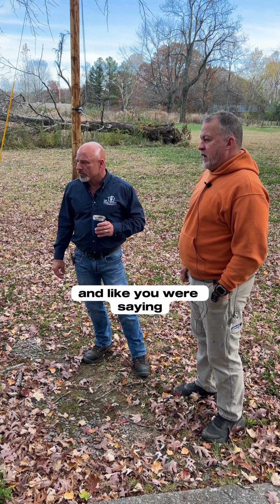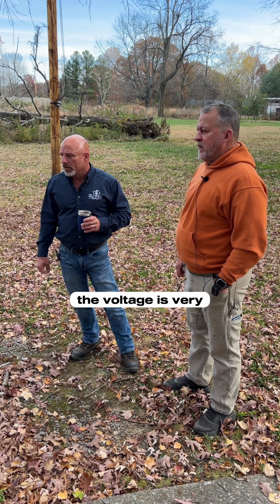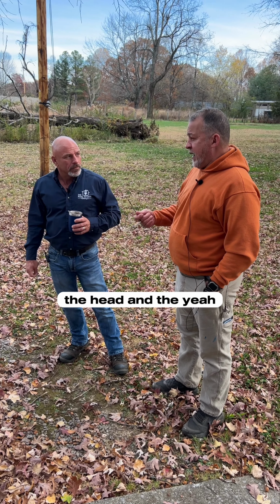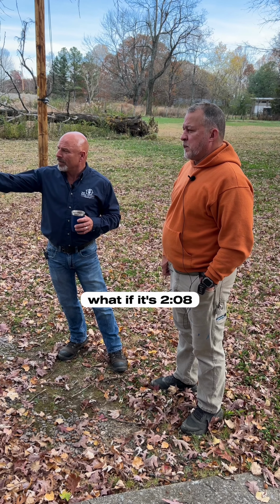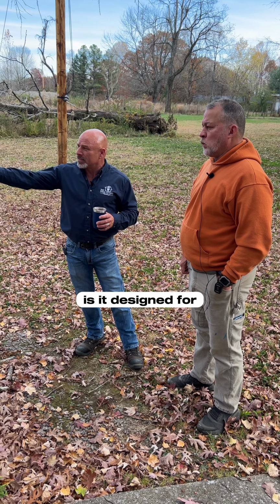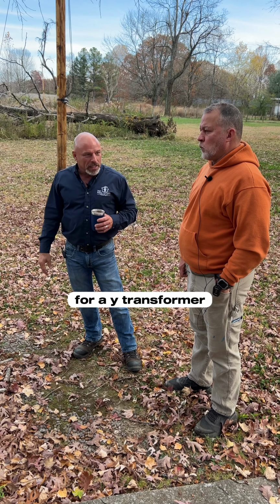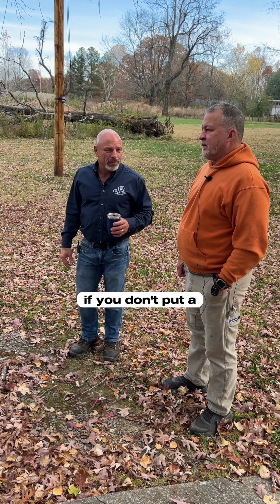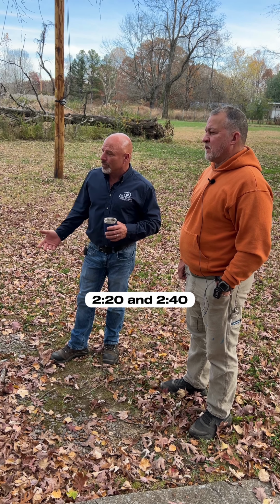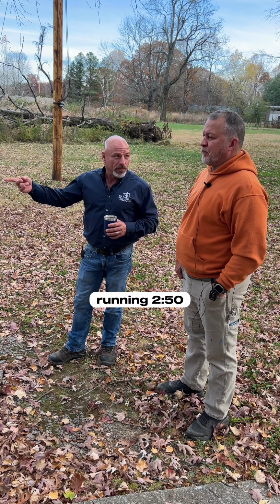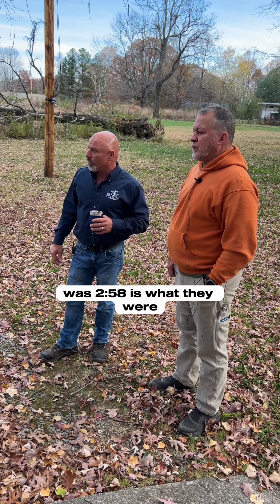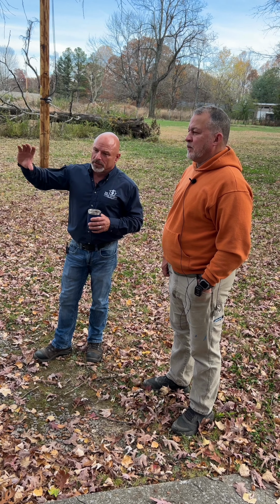And like you were saying, the voltage is very important to match the head and the unit. If it's 208, that tells us it's designed for a Y transformer, because that's what gives you 208. If you've got a Delta transformer, you're going to have between 220 and 240. Oh, and these are running 250 - I think it was 258 - because it was pushing 10% over the 240, and it's just burning up the boards.